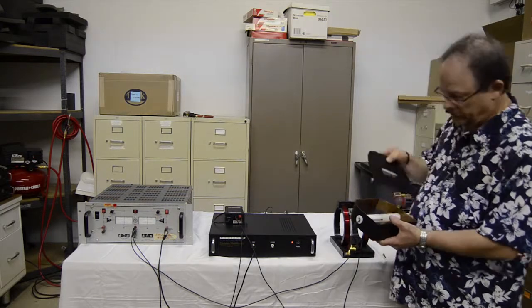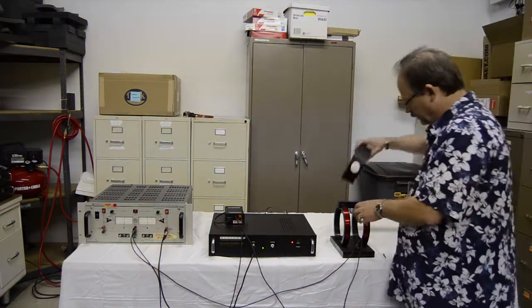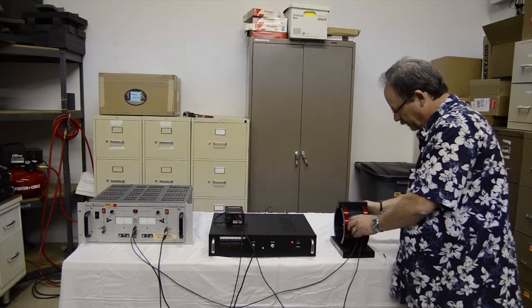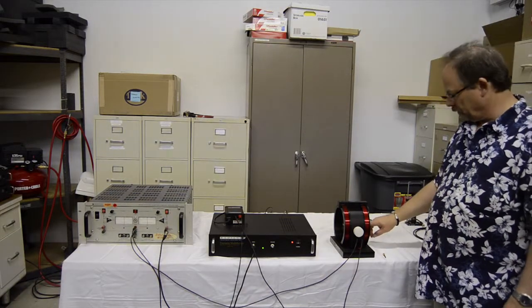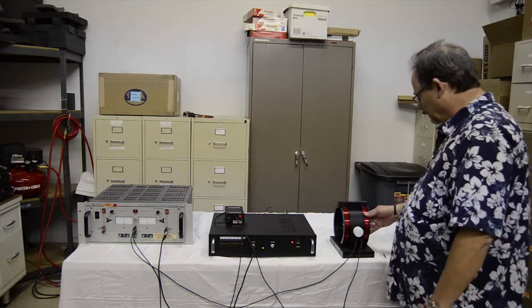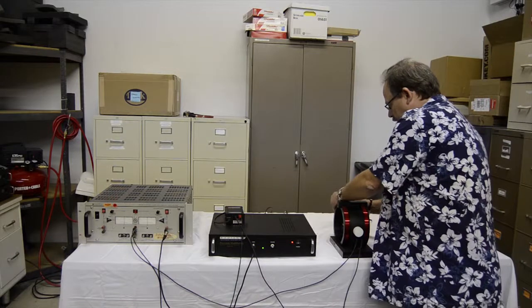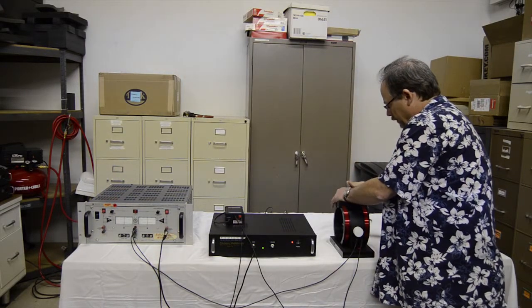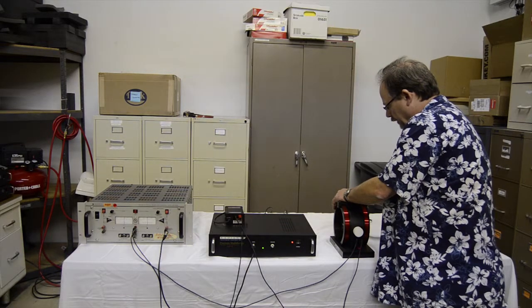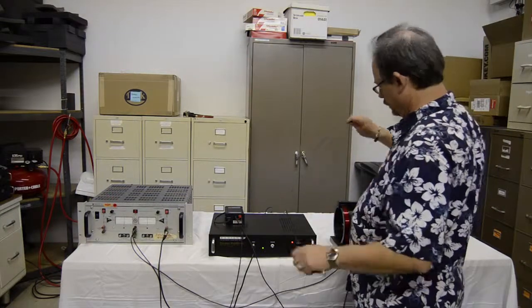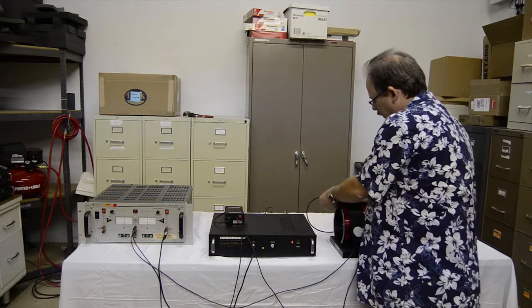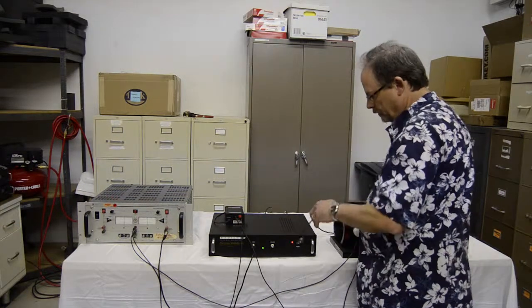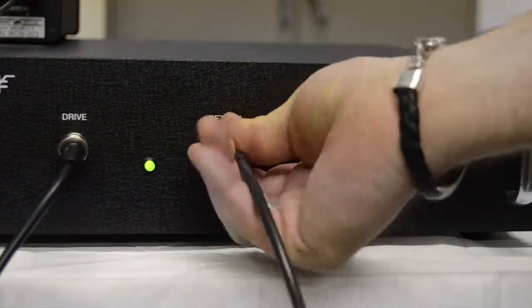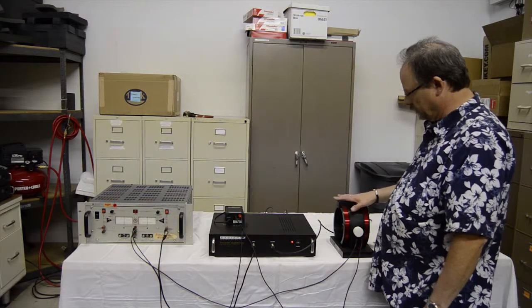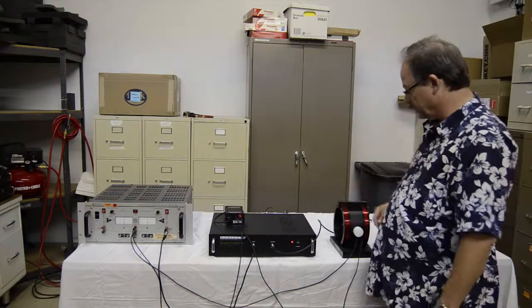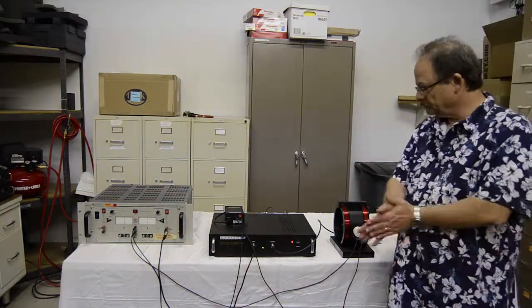Then the sample holder is closed, and the entire assembly is inserted into the Helmholtz coil. This ensures that the sample is sitting along the center line of the field generation. Finally, from the SMA connectors on the sample holder, we connect the grounding plug that was provided to one of the connectors, and you would connect the opposite connector, which is the signal and response connector, from the SMA plug to the return port of the tester, so that the charge induced in the sample by the applied field is detected at the return port of the tester. And well, good luck.